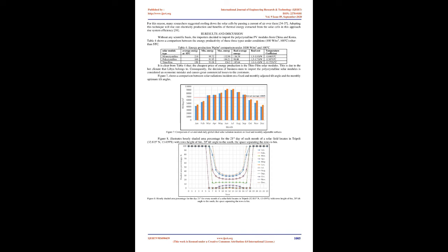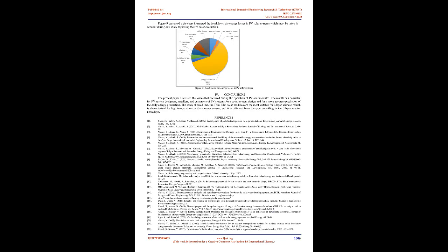As cell temperature increases, voltage decreases, and module conversion efficiency suffers. Other than temperature, module performance is also affected by sun irradiance. When sun is full, i.e. at irradiance of 1000 W/m2, module current is highest, and when there is less sunlight, module current decreases and so does conversion efficiency. Since sunlight intensity and module or cell temperature vary substantially throughout the day and the year, array MPP, current and voltage, also varies accordingly.